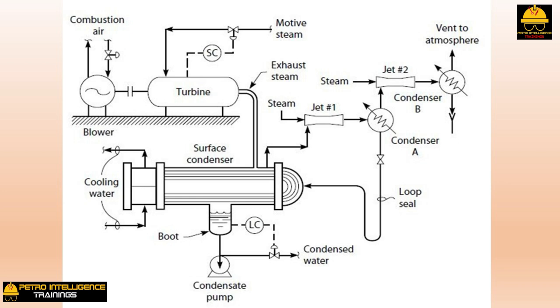Note that the vacuum measurements of 27 inches mercury and 14 inches mercury use the refinery vacuum measurement system, where 30 inches mercury equals full vacuum (0 mmHg) and 0 inches mercury equals atmospheric pressure. Thus 27 inches mercury vacuum is really 3 inches mercury absolute, and 14 inches mercury vacuum is really 16 inches mercury absolute. For practice, using your Mollier diagram with motive steam at 400 psig and 650°F — reducing the vacuum from 27 to 14 inches mercury results in a 13% loss in horsepower.